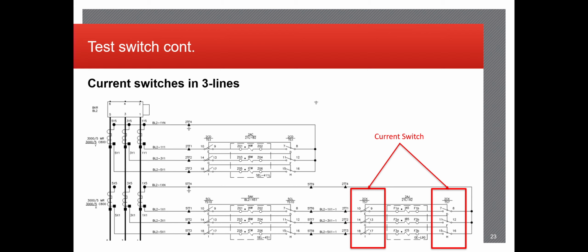We got an example of a 3-line that I discussed earlier, and the current switches that connect to this breaker's CTs. So you always look at the breaker CTs based on the polarity as well as what the ratio should be per the relay design. The polarity, you can tell, is the square boxes on the CT itself that will run directly from the field into the control house and go into a current knife switch. That will then go into, whether it's a relay or a meter, come out of it, go back into the knife switch, and then either loop back around to the neutral of the CT or to another piece of equipment if necessary.